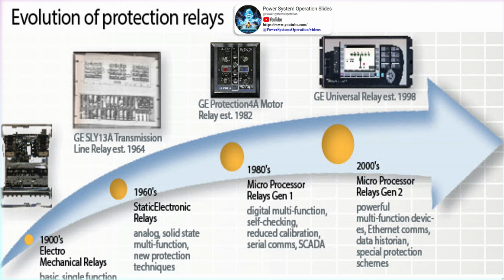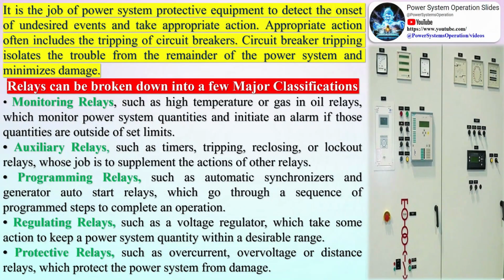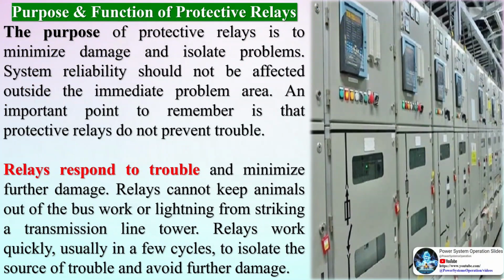Relays can be broken down into a few major classifications: monitoring relays, such as high temperature or gas in oil relays, which monitor power system quantities and initiate an alarm if those quantities are outside of set limits. Auxiliary relays, such as timers, tripping, reclosing, or lockout relays, whose job is to supplement the actions of other relays. Programming relays, such as automatic synchronizers and generator auto-start relays, which go through a sequence of program steps to complete an operation. Regulating relays, such as a voltage regulator, which takes some action to keep a power system quantity within a desirable range. Protective relays, such as overcurrent, overvoltage, or distance relays, which protect the power system from damage.